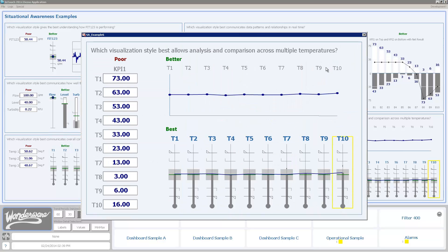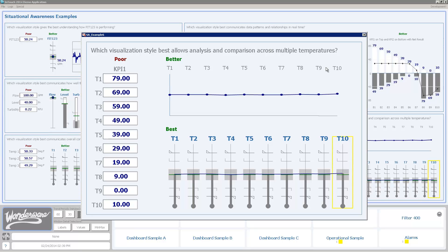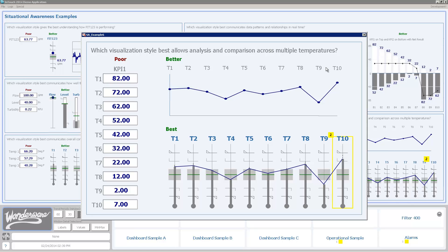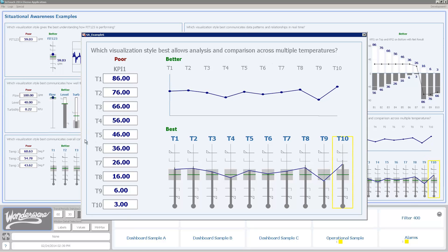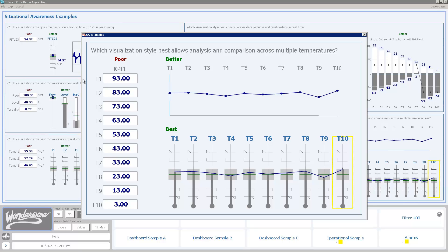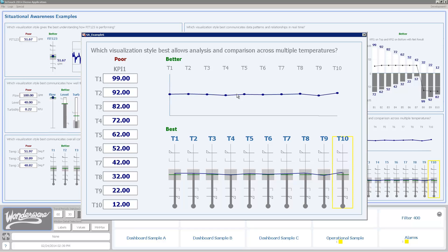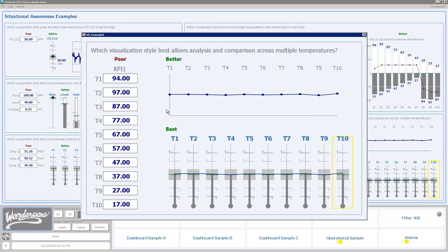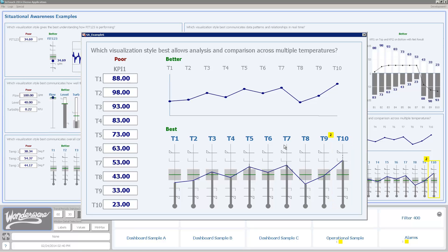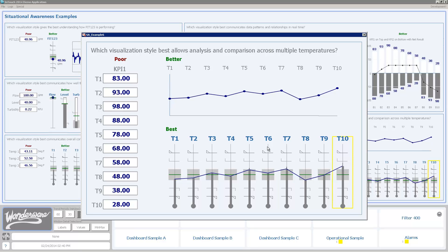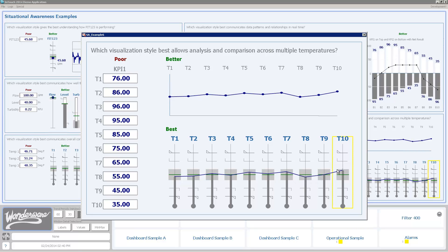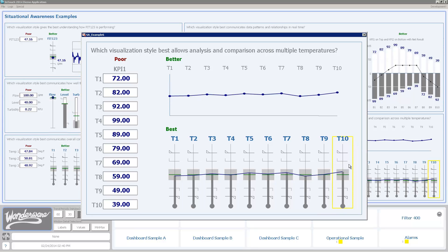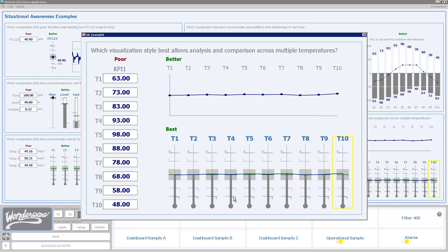And my last example that we're going to show here today, I'm showing multiple temperatures around a vessel. I've got 10 temperatures that are around this vessel and I'm trying to understand if there's anything that's deviating. These numeric values require you to go and inspect each individual number and understand what they are in relationship to the others. It's a really slow and error-prone process by using that. In this parallel coordinates chart here, where each point is a different variable and I've used a connector line to put them, I can basically see where any deviations are. In the bottom where I've labeled best, I've got them all as meters so I can know where they sit with regards to whether or not they're within expected ranges. I've connected them so I can see lines, because the human mind is very good and adept at being able to see changes in line direction. I've also got information like alarm information. So I can see temperature 10 recently was an alarm but it's back in normal state now.